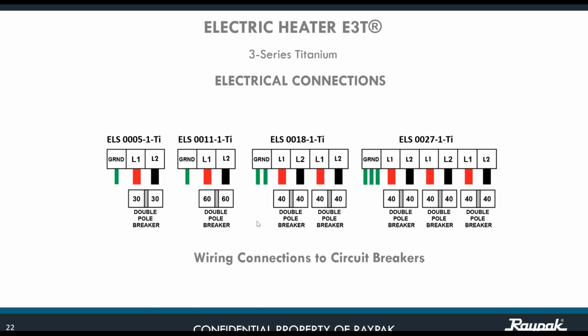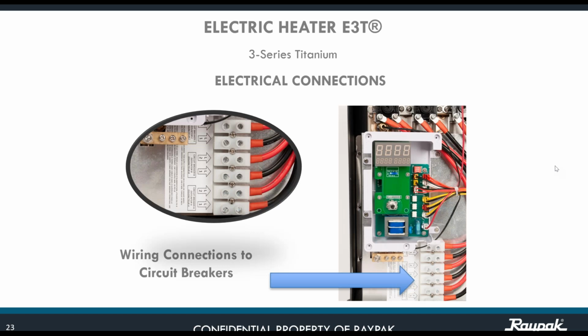And for the 27, now you start to see three sets. You have three grounds, three L1s, and three L2s, all of them connected to their double pole breaker, those sets of L1, L2. Okay. This is the point of entrance for the L1, L2. You see it right here. And this is the bar for the ground connections. All of them are going to be beneath the CPU. That is, let's say, the command center for this unit.